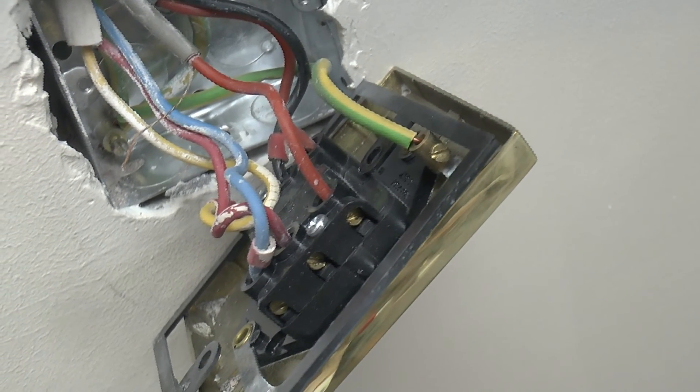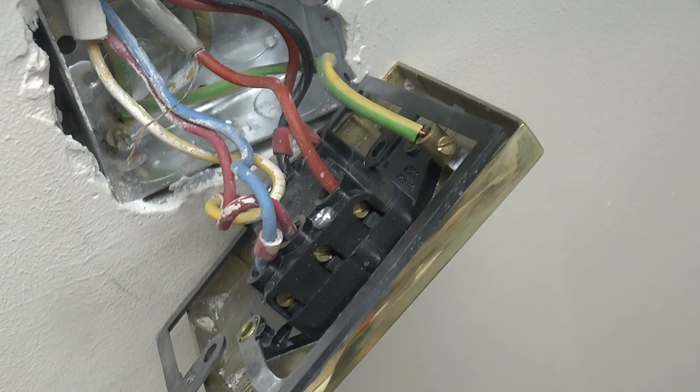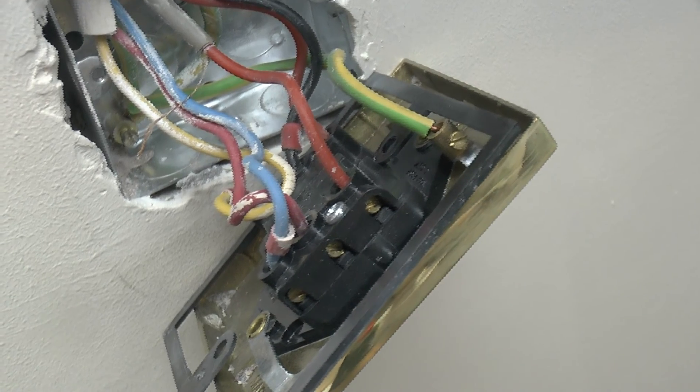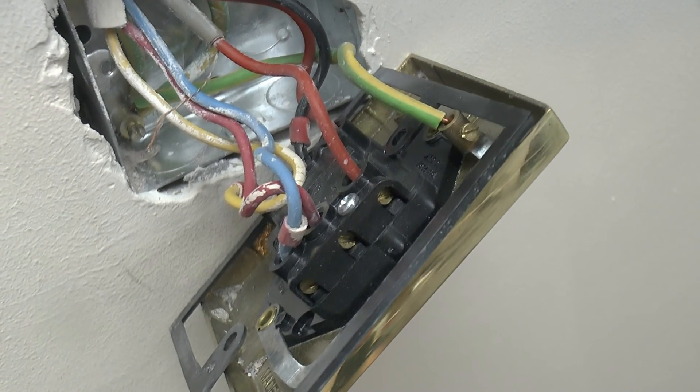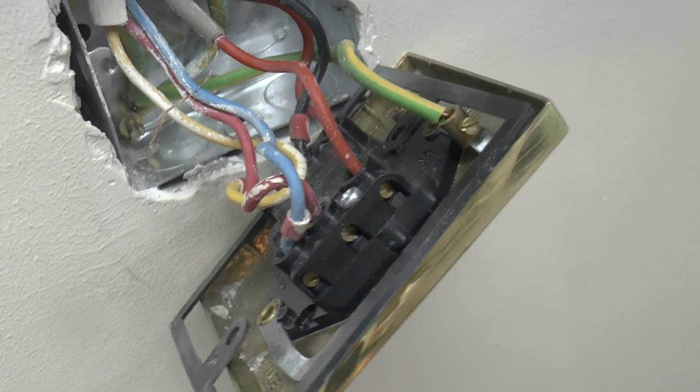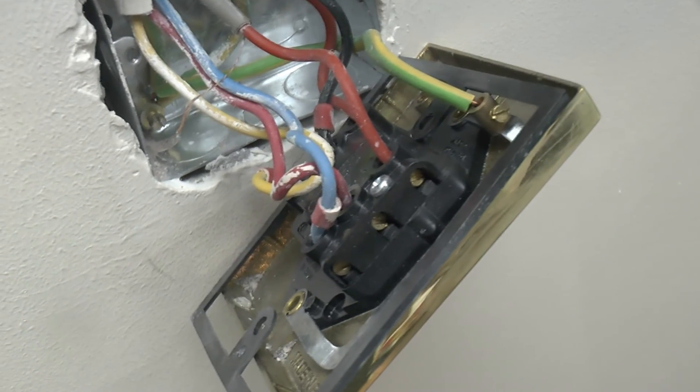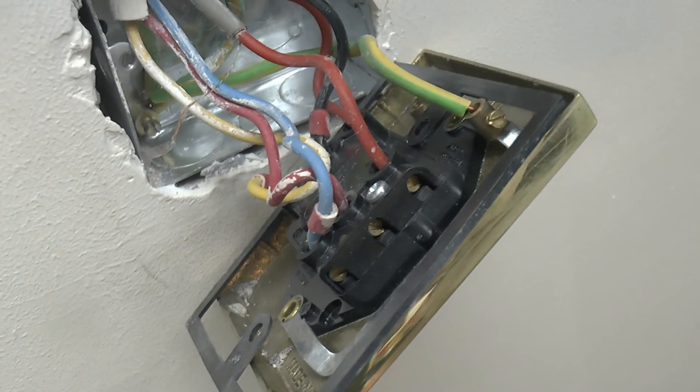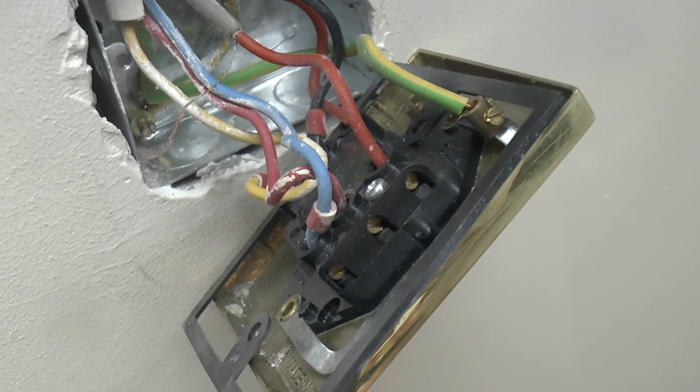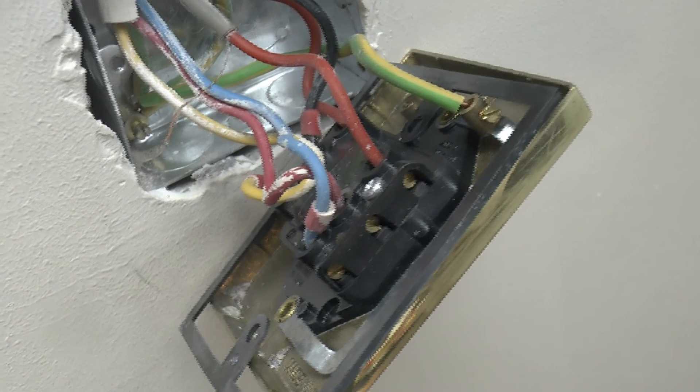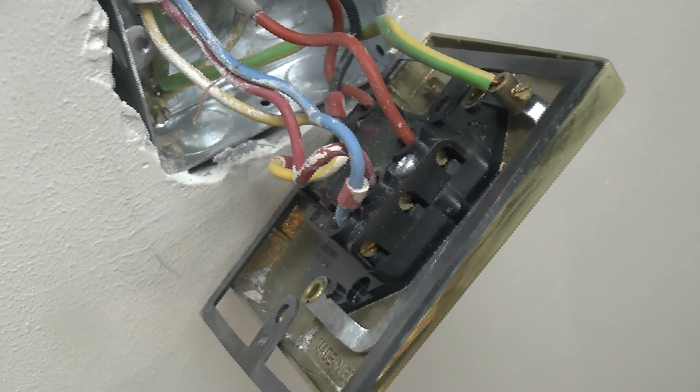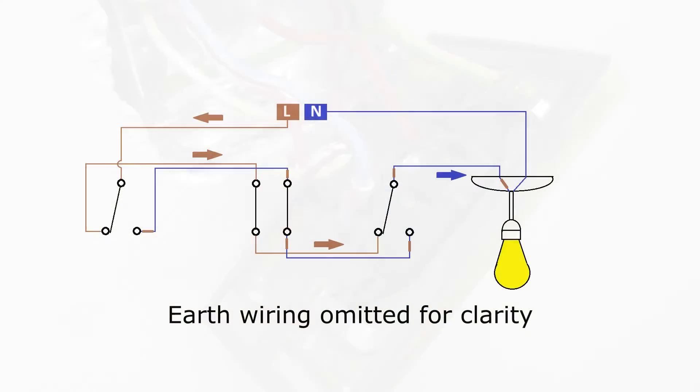If two-core cable is used for the line or the switch line, the second core can be used to bring a neutral conductor to the switch, if the switch is a fancy electronic one or a time switch that needs it. Otherwise, it's probably best left unused.